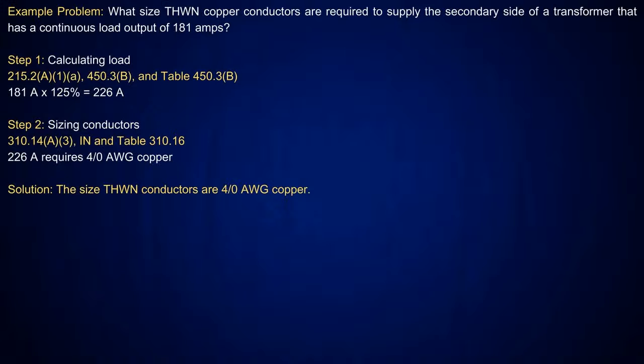125%. In this case, it's a feeder, so I'm going to apply 215.2(A)(1)(a), and that's where I get the 125% at. So I take 181 amps at 125%, which gives me 226 amps. Then I need a conductor for that. Well, I go over to Table 310.16 and pick up the 75 degrees C column. The next size above that is 230 amps, which is a 4/0 conductor.